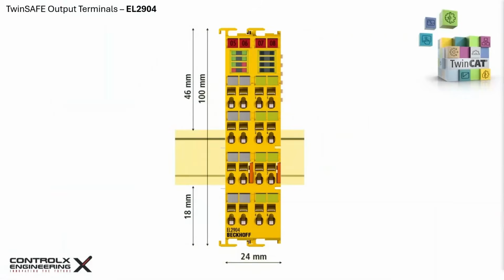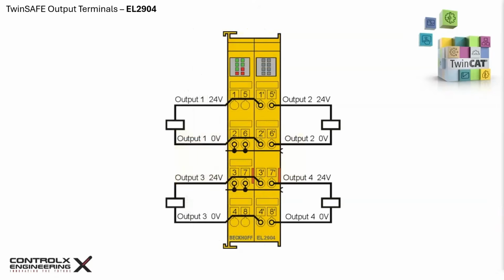The EL2904 uses Beckhoff's standard compact terminal housing, but in the wider 24mm format, because it contains 4 safe output channels and the associated power electronics. The housing is made of polycarbonate like the other terminals and is designed to mount on a standard 35mm DIN rail using the standard Beckhoff locking mechanism. This diagram shows the 4 output channels. As you can see, the output connection points reside on the right half of the terminal. For wiring, the EL2904 supports solid, standard, and ferruled connections with wire sizes from 28 gauge to 14 gauge, depending on conductor type. When connecting a single actuator via its own continuous cabling, the maximum permitted cable length is 100 meters or 328 feet. The EL2904 can safely drive actuators such as relays, contactors, guard door interlocks, signal lamps, etc. Each output channel can drive a load with 500 milliamp max.